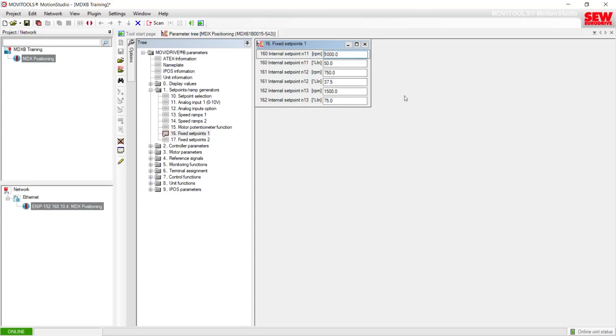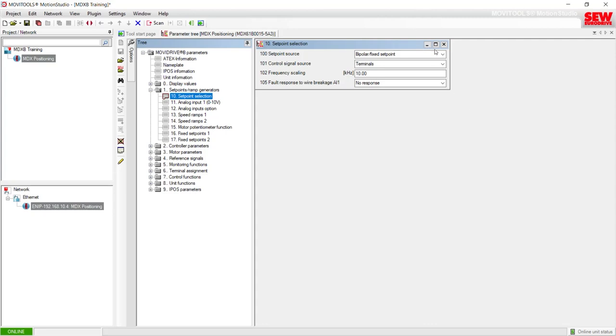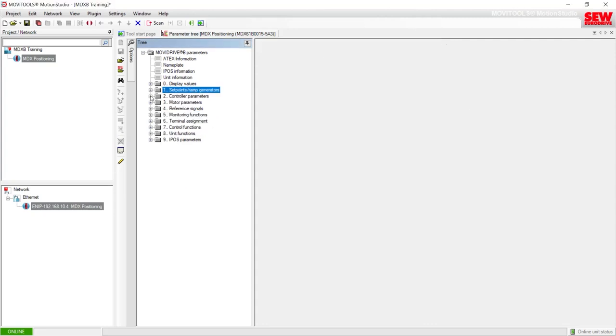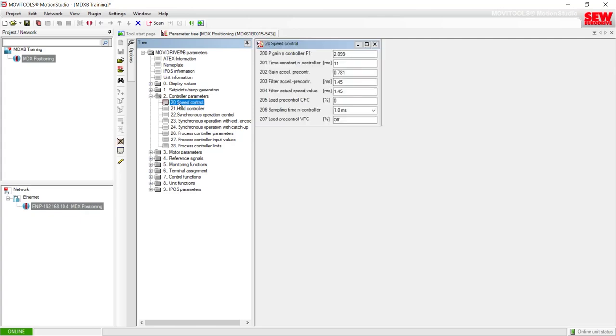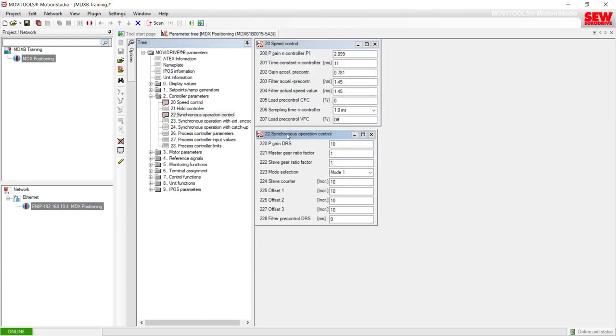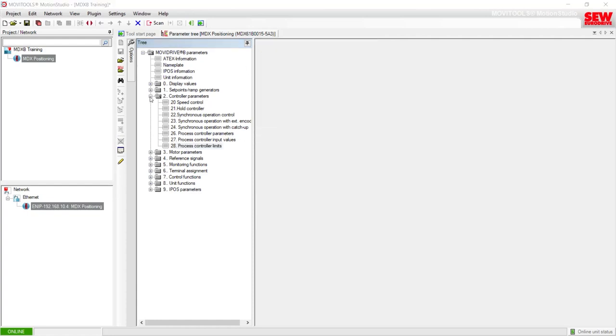Let's look at some of the other parameter groups of the MOVIDRIVE. Folder 1 covers speed ramps and fixed set points, with item 10 being the set point selection for terminals or field bus. Folder 2 is the controller parameters — commonly where you'd go for custom tuning adjustments in item 20, Speed Control. Items 22 through 24 are only for when you have a DRS11B option card installed for synchronous operation, and items 26 through 28 are for an external PID controller.